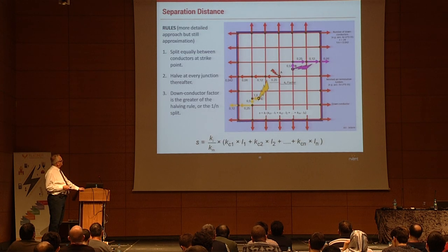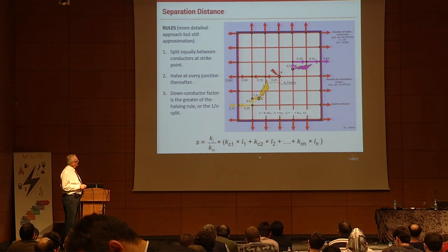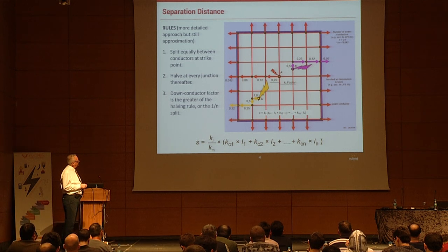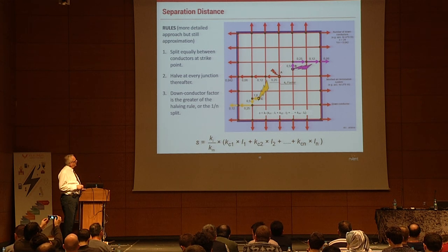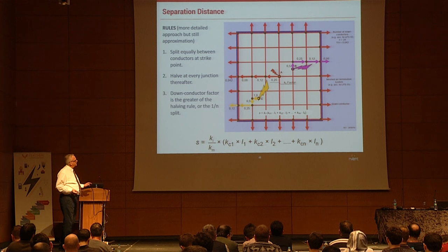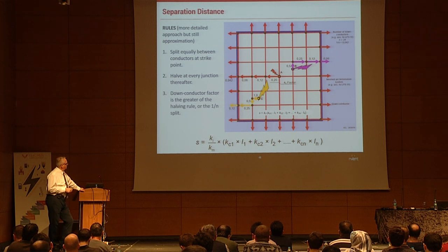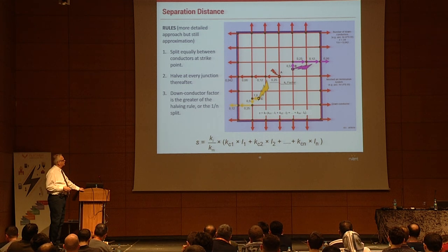For a block building with a more complex network, if the strike hits in the middle the current splits evenly in four directions — a quarter of the energy going each way. At every junction point after that, you get half of that. The formula becomes more complex, but these examples are directly from the standard so you can refer to them.